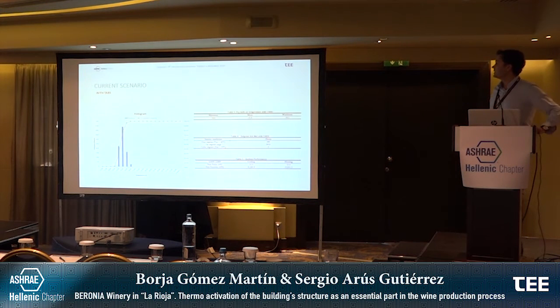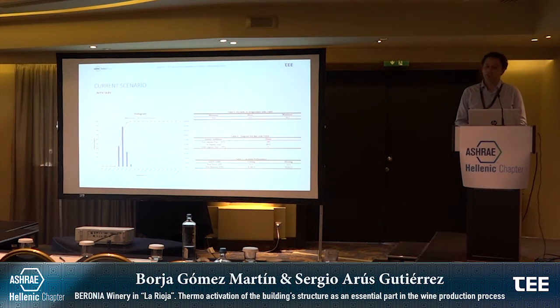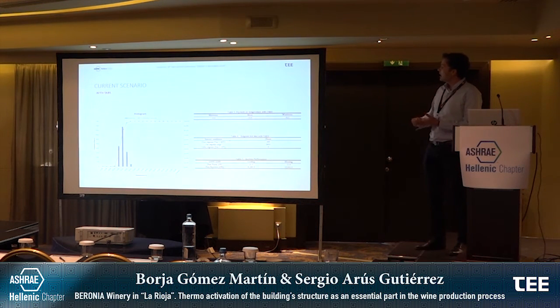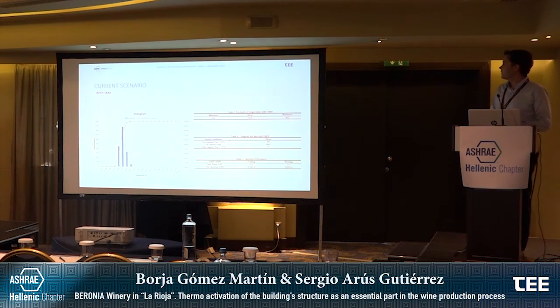And this is what happens with TABS, like magic. It changed a lot, as you can see, and with very, very low operation cost. So out of this 8,760, we literally have just more than 300 hours outside the set point. And actually these 300 hours are just at 16.5 degrees. So it's negligible. We can say we are 100% sure that we are achieving our goal with very, very low operational cost and environmental cost with these taps.